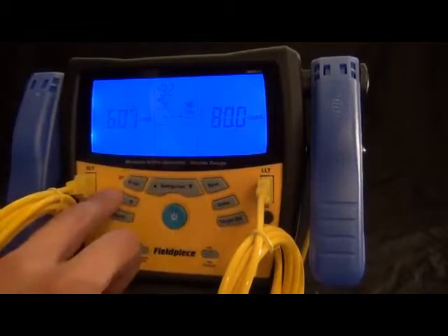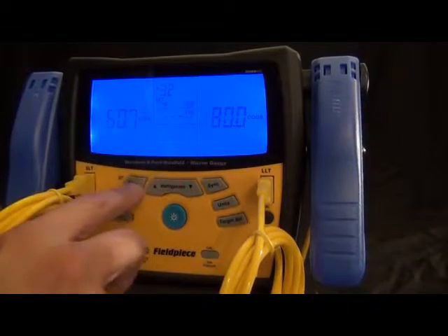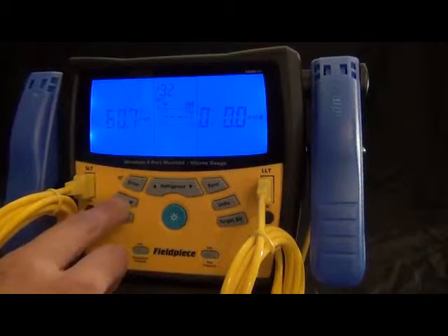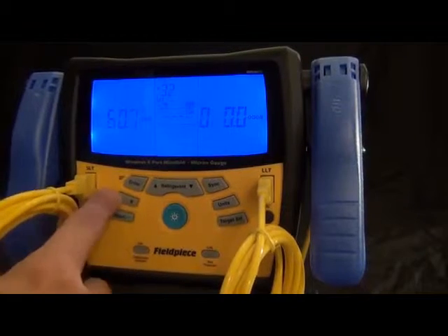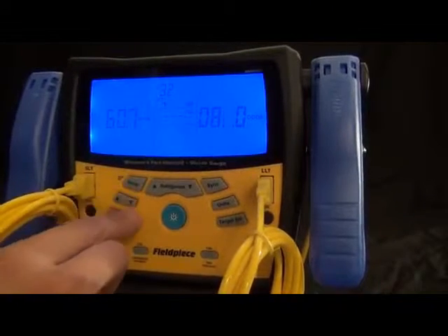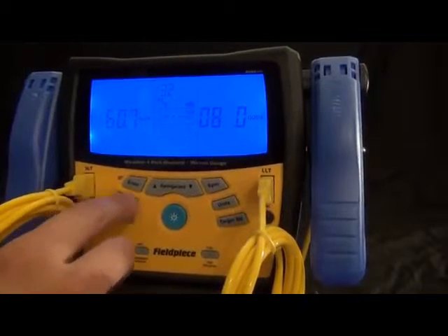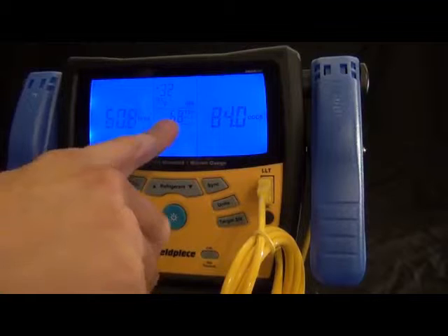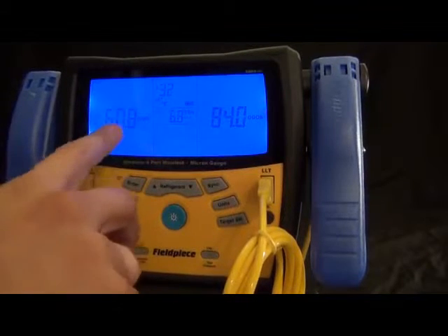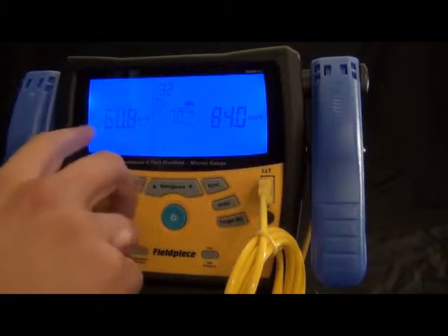Now, this target superheat is for fixed restrictor systems to tell you what your superheat is supposed to be. So, for example, if I got a 60.7 indoor wet bulb, along with an 84 degree outdoor ambient temperature or dry bulb, I would get a 7 degrees of superheat. And, that's that.